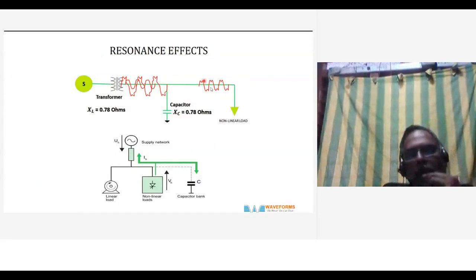So this is a serious problem. When it is an inductive load, capacitance can solve the problem of power factor. But when you have a non-linear load, the capacitor does not act like a capacitor. It acts like a harmonic amplifier, interacts and amplifies the signal. So this one shows the linear load, the capacitor bank and the non-linear load, and how non-linear load causes problems in the supply and how harmonics flow to the network.